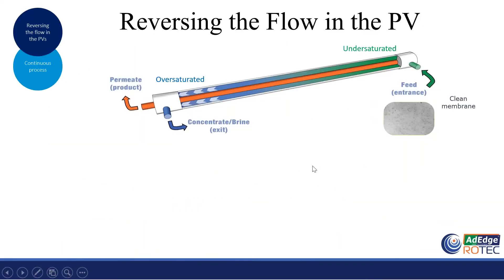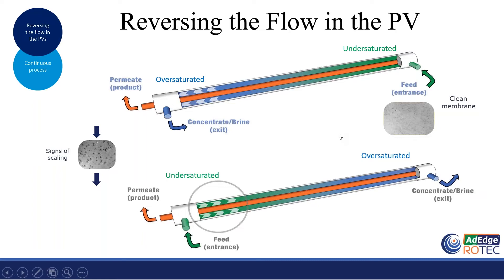In a conventional pressure vessel, feed water flows from right to left — from the green part to the blue part. Then, prior to the induction time — when we start seeing signs of scaling — we reverse the flow in the exact same conventional pressure vessel. Now the feed water flows from left to right, from green to blue again. But the area that was previously circled — where concentration was building — is now rinsed by an under-saturated solution, which removes the scale if it ever formed.